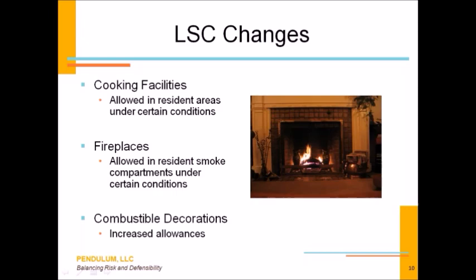In a means of egress, you can have combustible decorations that comprise up to 30% of the wall space. Now, I don't know about you, but if it's me and it's my facility, I'm still going to limit my combustible decorations, probably a lot less than 30%, but that is what the code prescribes. In a resident room, you know, especially in our long-term care facilities, we see that home-like environment evolving. I see a lot of combustible material in resident rooms in nursing homes, and maybe that's sometimes present in hospitals and other healthcare facilities. But the bottom line is you're allowed to have up to 50% of that wall space to include combustible decorations. Now, again, I try to limit it as much as possible, but sometimes there are cultural elements that you need to consider.